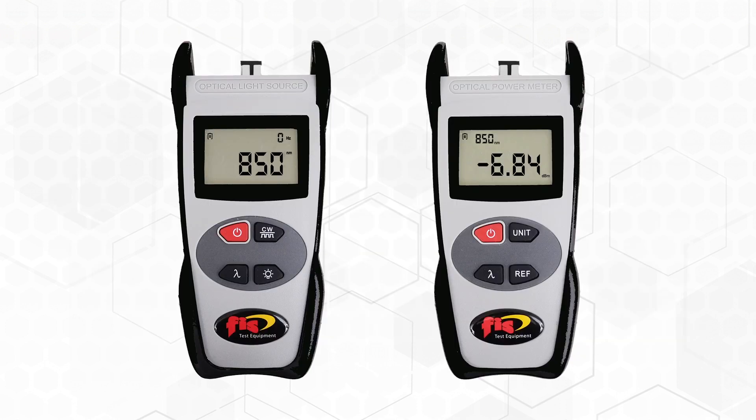The power meter and light source, called a test set when both are contained in the housing or presented together, measures only the net loss of light or the attenuation in a length of connectorized fiber. This is perhaps the most popular test performed.